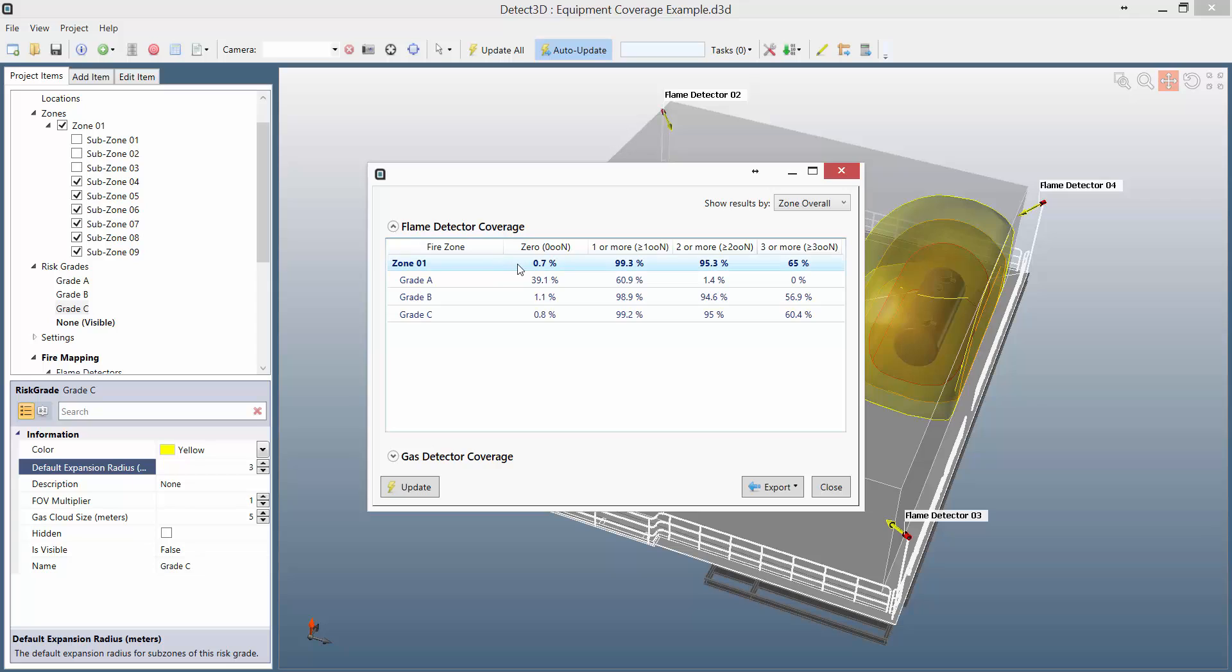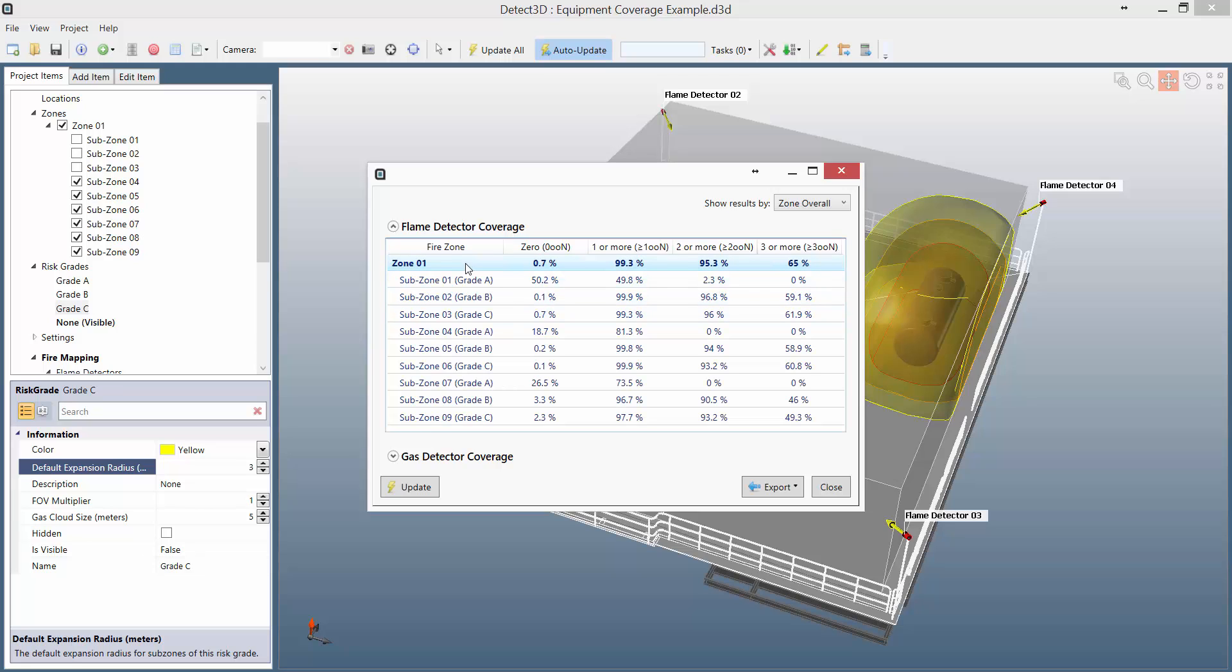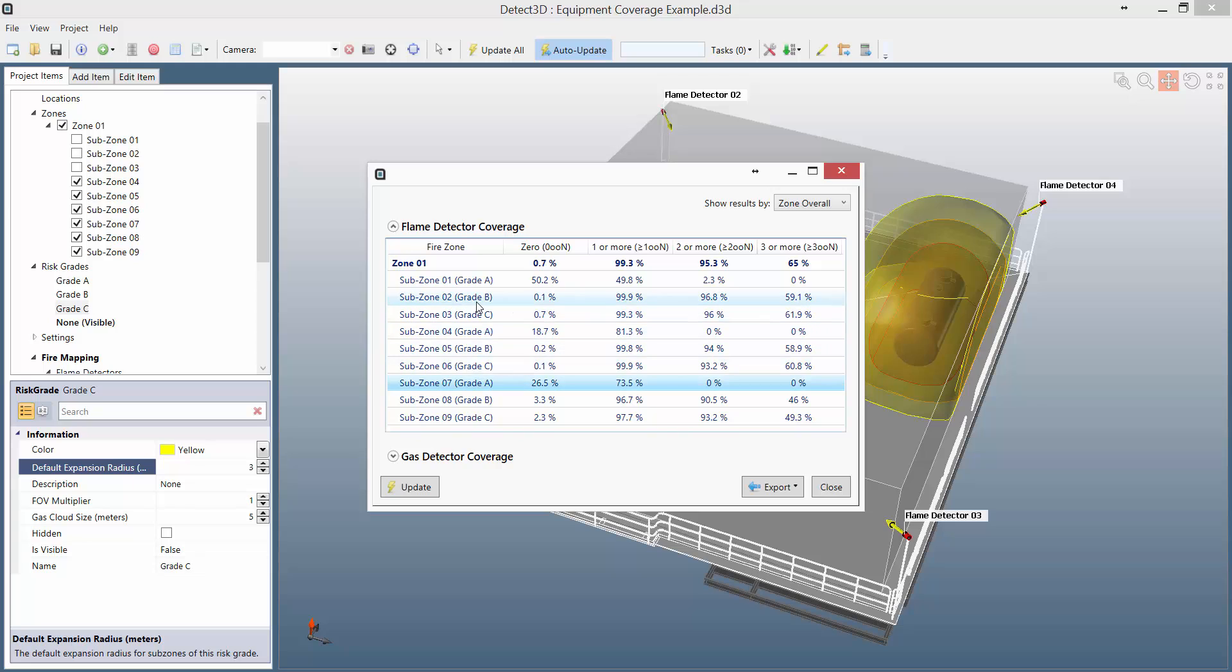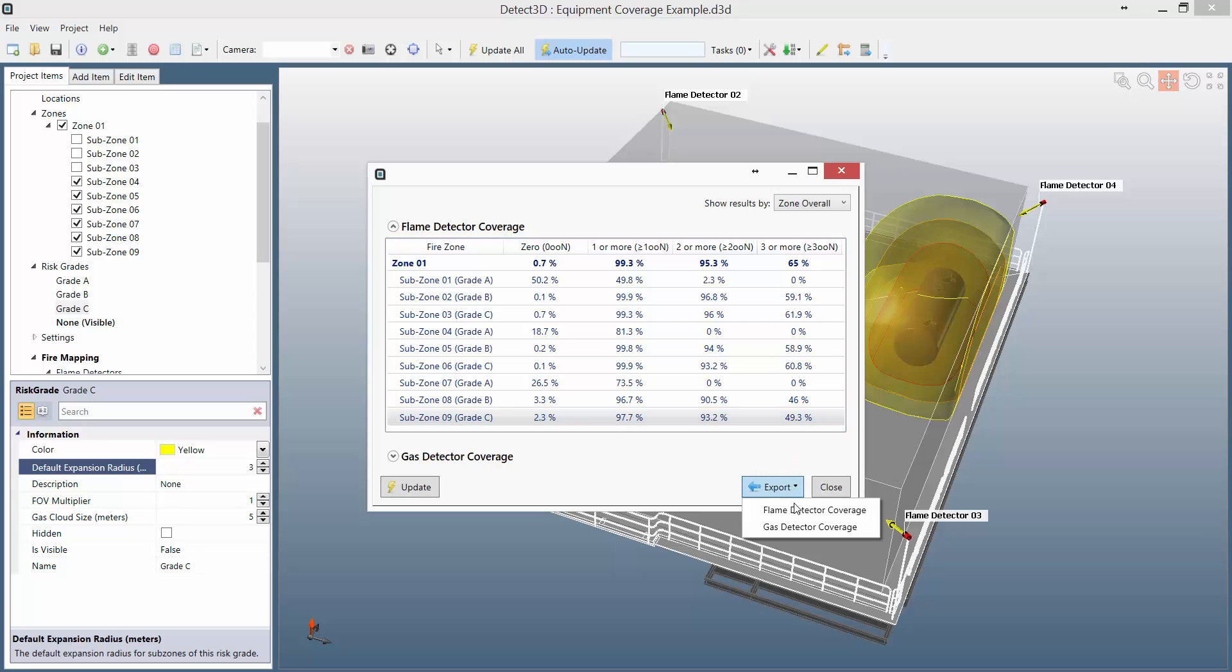I can see here the overall risk grades. Clicking the zone again will now show me the individual coverages of each subzone. You can see the general pattern that the coverage for risk grade A areas isn't as good, and that's because you're looking at a smaller fire, whereas for B and C you've got very nice coverage indeed. You can of course export all this data to an Excel spreadsheet just by clicking export and flame detector coverage.